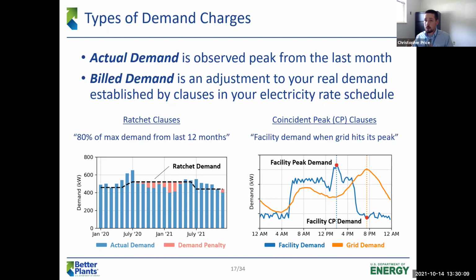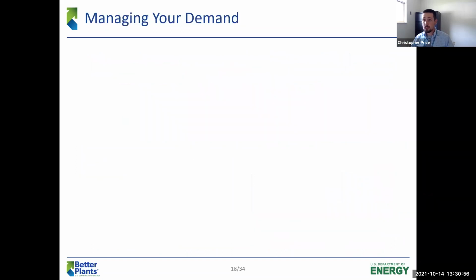Also related to this, some companies will charge you for coincident peak demand. During summer months, a utility would call four peak events, and your facility's average demand at each one of those peak times is averaged and then used to set your 4CP demand charges for the next calendar year. So you could hit a peak theoretically in July of 2020 and then not see the result of that peak until January of 2021 and then pay for it all the way through to 2022. So making sure that you avoid those peaks is pretty important to minimizing your billed demand. So how do you manage demand?